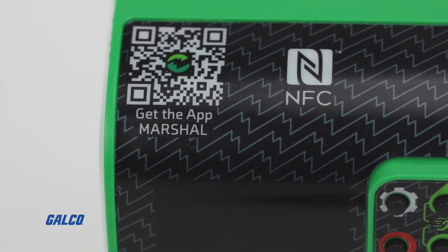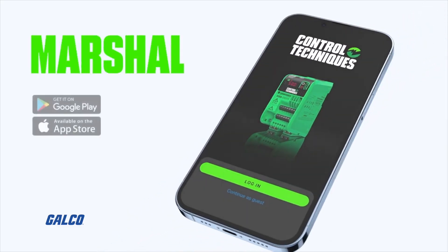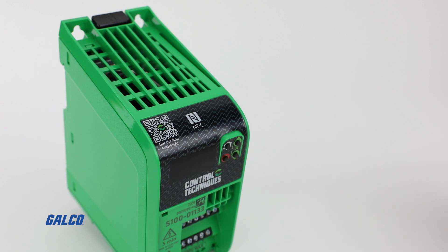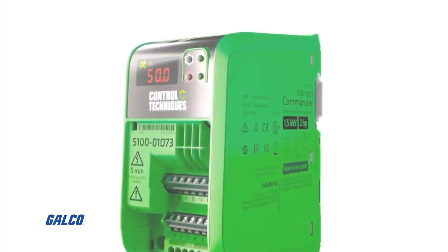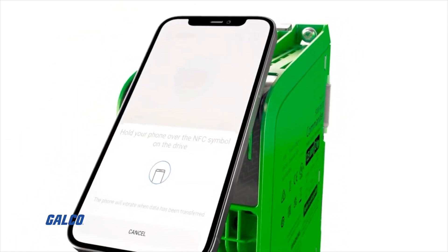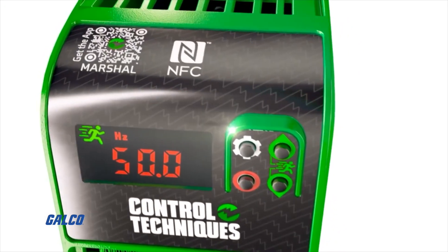Control Techniques is also the first drive supplier to implement NFC technology as standard on the drive and offer the Marshal app interface at no extra cost. Once you connect your smartphone to the drive through the app, you can transfer data in less than half a second, making connecting, commissioning, cloning, and sharing drive parameters and configurations as easy as app, tap, and go.